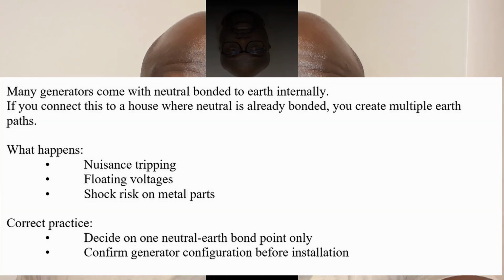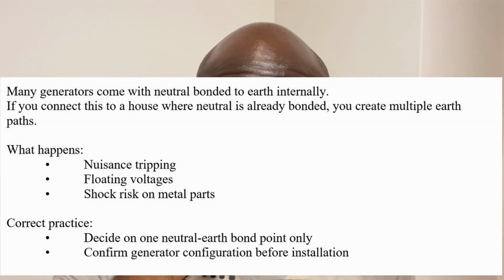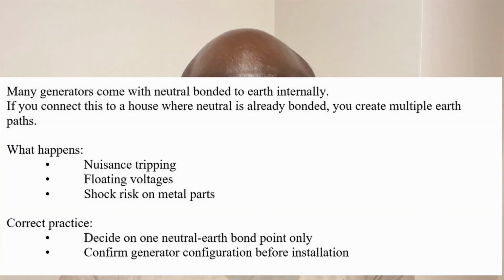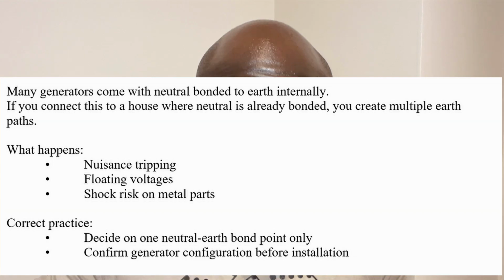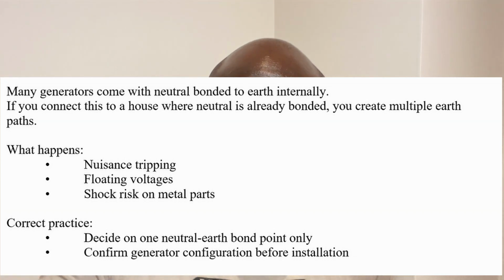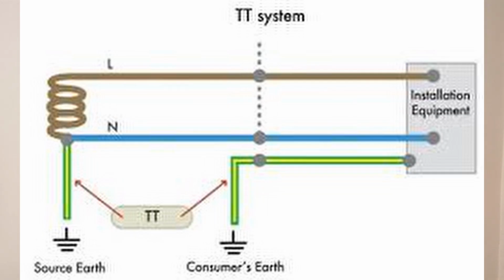Okay, now this is the correct practice. You have to decide on one neutral earth bond point only. Confirm the generator configuration before installation. Typically in Ghana, this should not be an issue unless the electrician is not experienced and has done something wrong, because typically in Ghana, the ECG is a TT system. So the neutral within the distribution board after the meter should not be connected to earth. So it shouldn't be a problem if, when you are on generator supply, that generator neutral is connected to earth internally. It shouldn't be a problem unless the electrician has made a mistake. But I'm just raising this as an awareness.